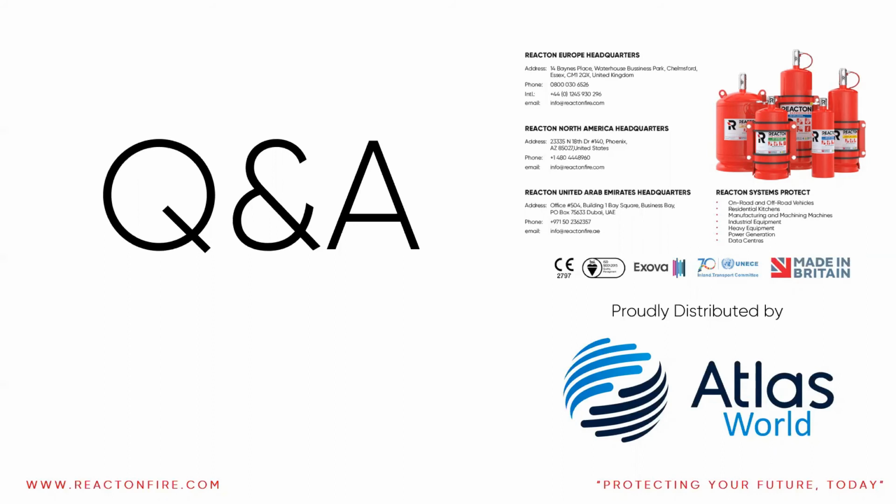Two questions in here on maintenance from Hilary and Chris. After a system has been installed, does it need any ongoing maintenance or servicing, and what would be the frequency required? Yeah, we highly recommend having the system serviced. It's part of the warranty stipulation, and especially in a piece of machinery, for example, you're going to be doing your daily operator checks, just making sure the system has pressure. It's very much a visual check there daily. And then every 6 to 12 months, we insist on the system being serviced by a trained professional.